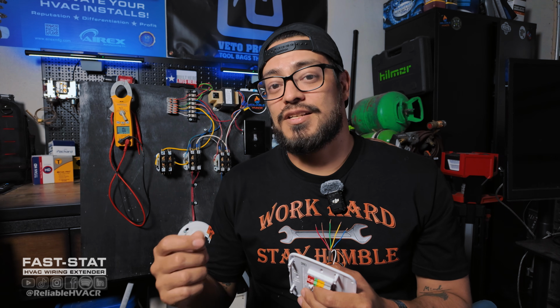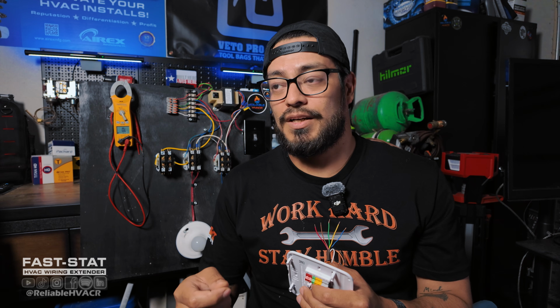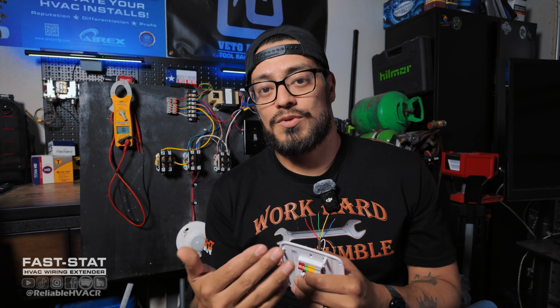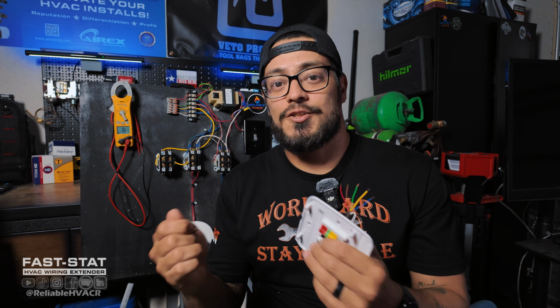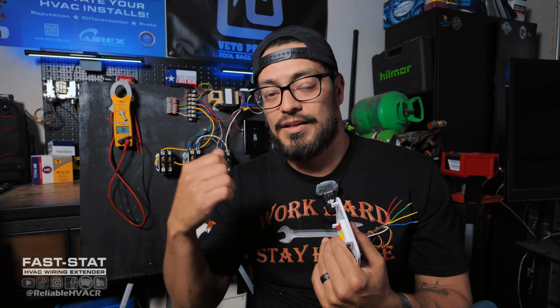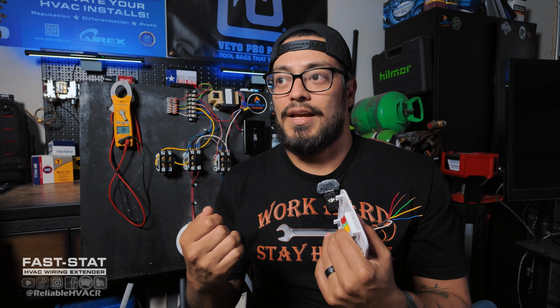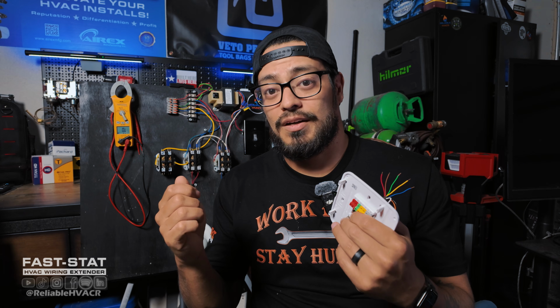If you check across and you do get a voltage reading of 24 volts, because that's what's going through there, then it's open, because you're grounding out the other side and you have a hot side on the other. And like I said, if you don't have a tone or you have resistance OL, you need to make sure that that safety is not tripped due to low charge or high discharge temperature. You're going to have to make sure that when you check your pressures, that is not an issue.